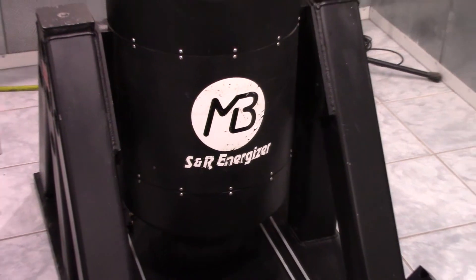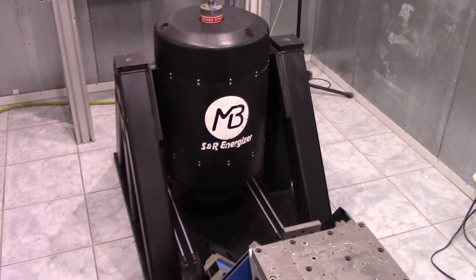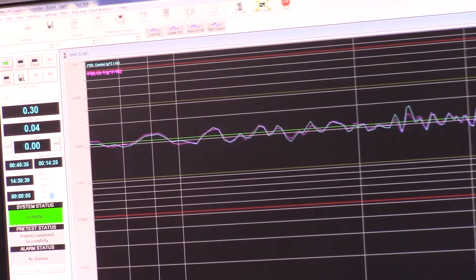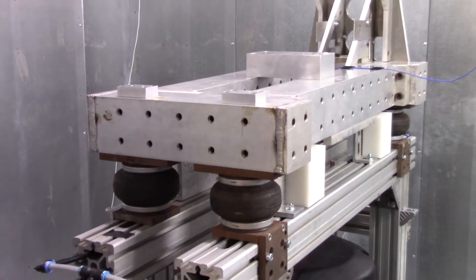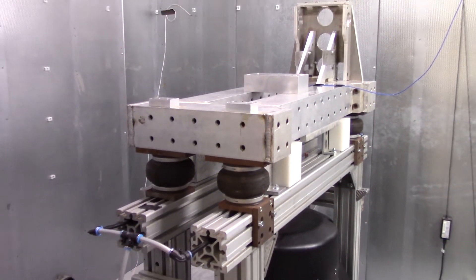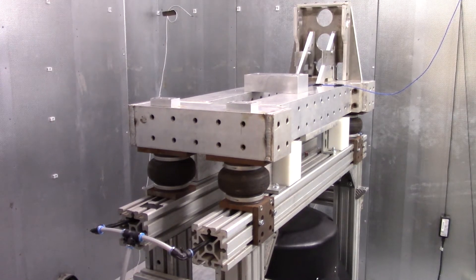Even if the lab is accredited, it's always a good idea to verify that the noise issue is not fixture or shaker related. Ask to see the resonance performance for the fixture and the sound level performance for both the shaker and the fixture. Once you have established that the shaker and fixture sound level are acceptable, the next step is to identify the source of the sound and the frequency range in which it is exhibited.